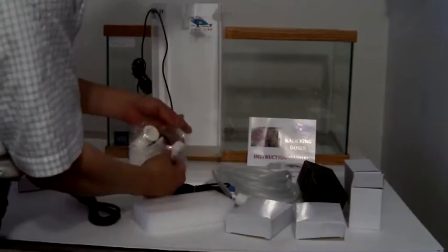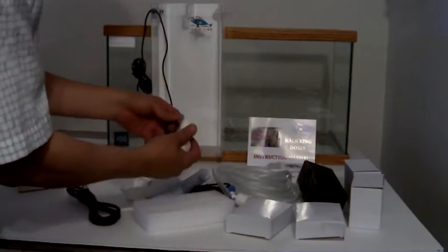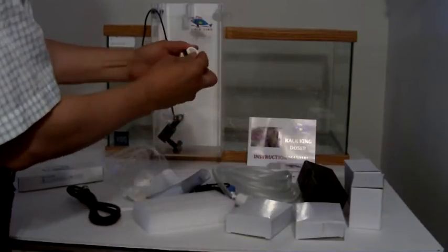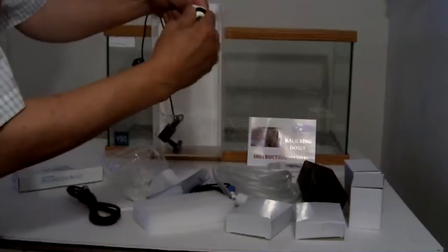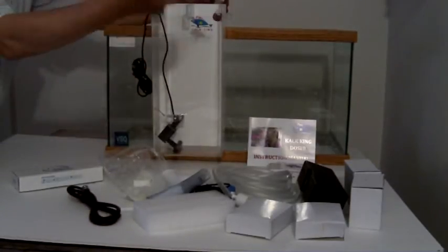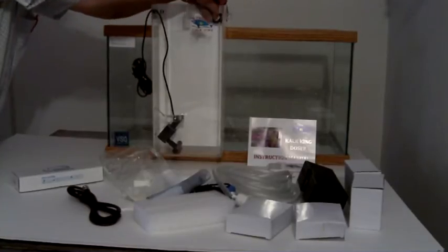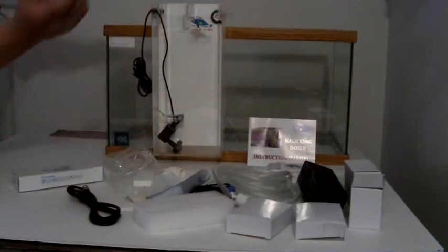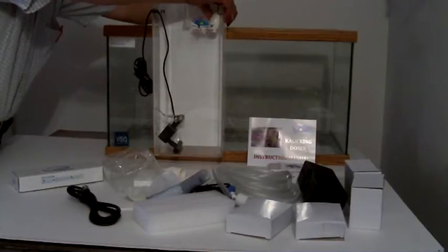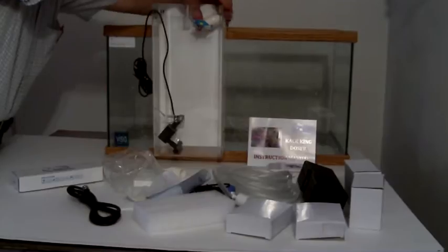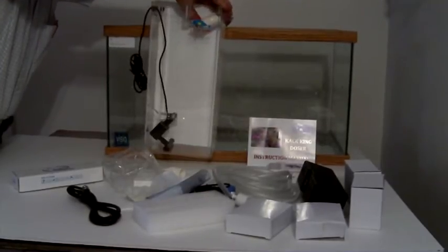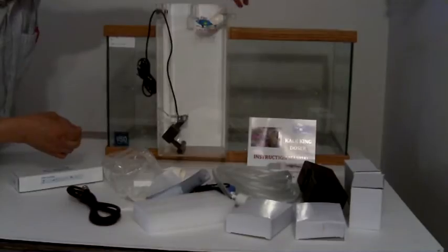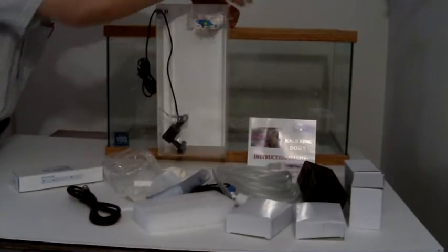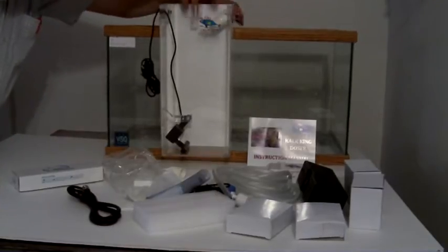Okay, the first thing to set up will be the reaction chamber output tube. So basically it has a black O-ring. So you just plug it over here and put the O-ring into it, and then you just screw it in. And actually, since this one is not pressurized, you can really just hand tighten it. The trick is to make this L tip about a 45 degree angle, and when it's tight, it's okay.